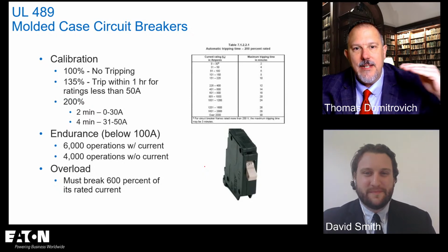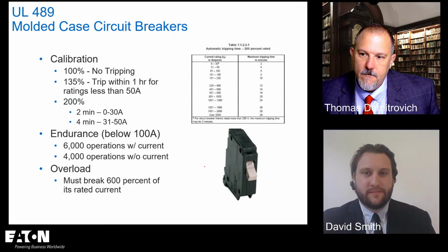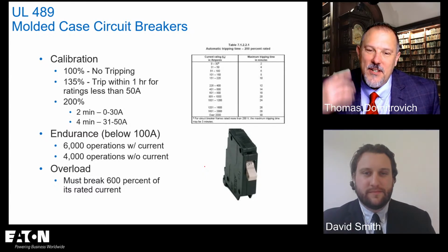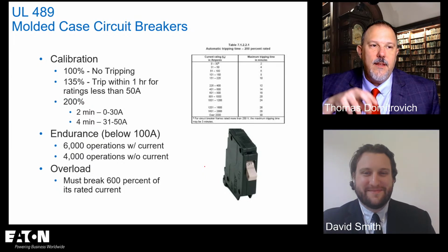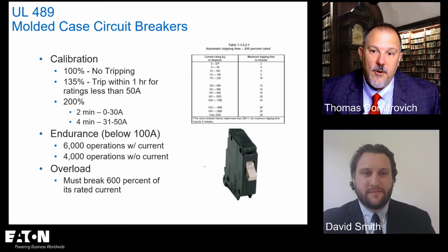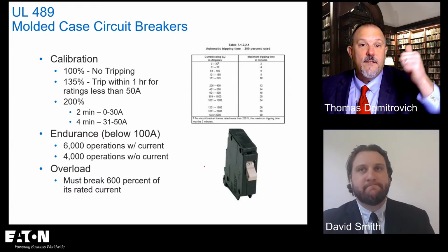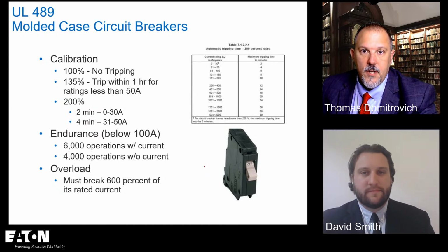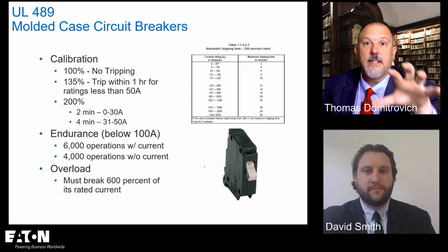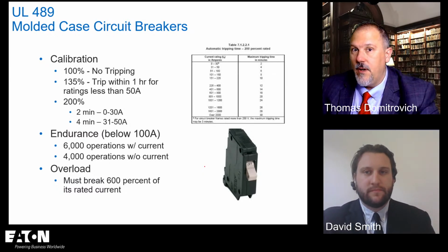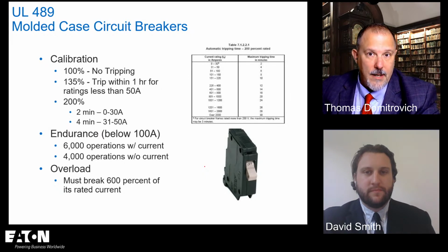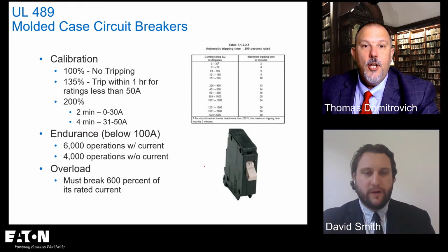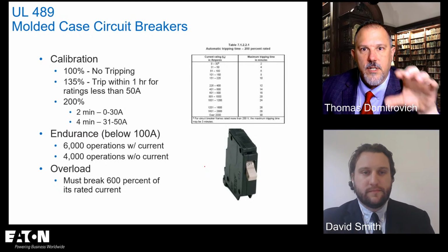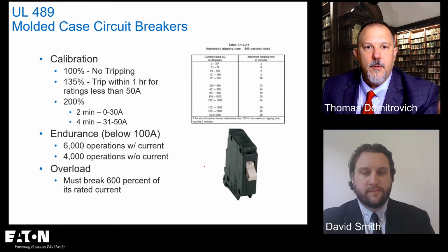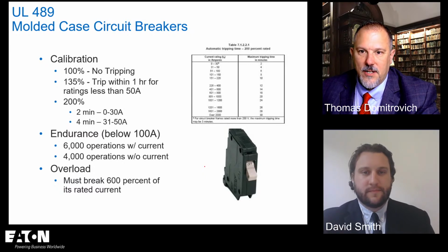So molded case circuit breakers are listed, and I said the AFCI circuit breaker is the most tested circuit breaker on the block. You have UL 489, which is the standard thermomagnetic circuit breaker. You have UL 1699, which is for AFCIs, that's the arc detection. If you have GFCI, you have UL 943. If you have GFPE, it's 1053. You have UL 1999, I think it was, which looks at the brains inside to make sure you don't have any problems. I think they call it UL 1999 because of the Y2K issues that we were worried about, I don't know.